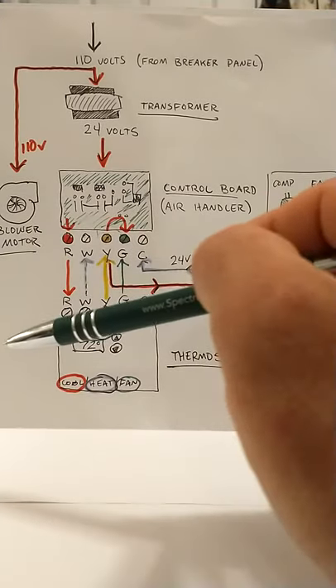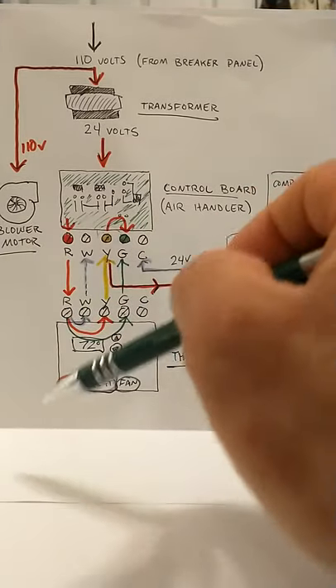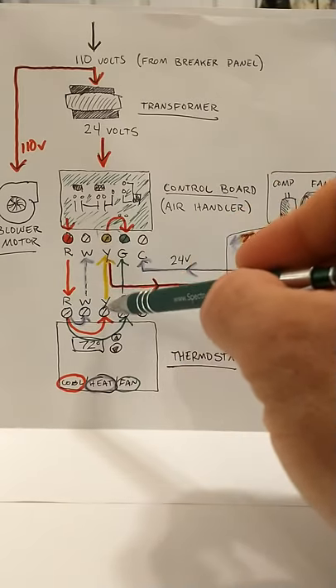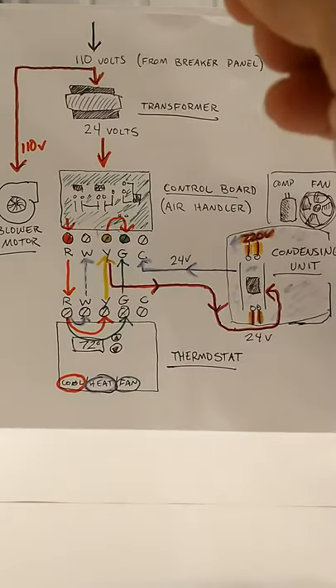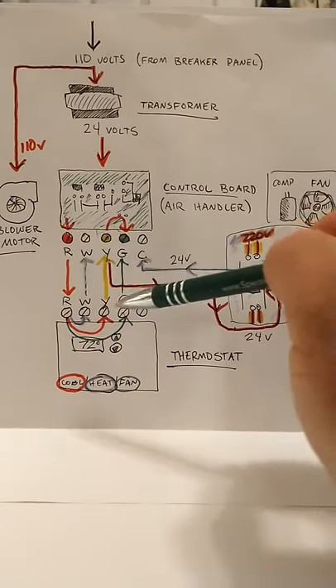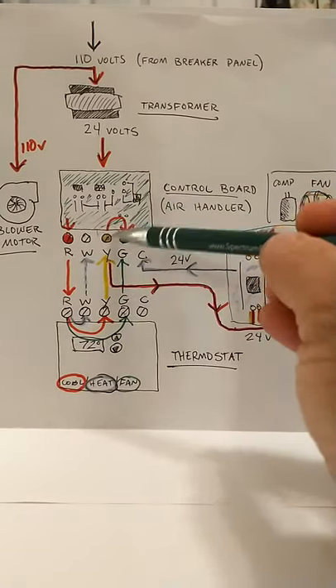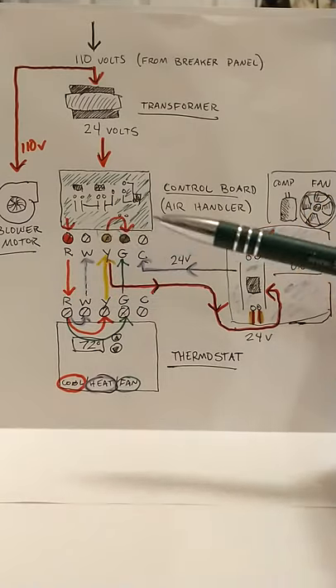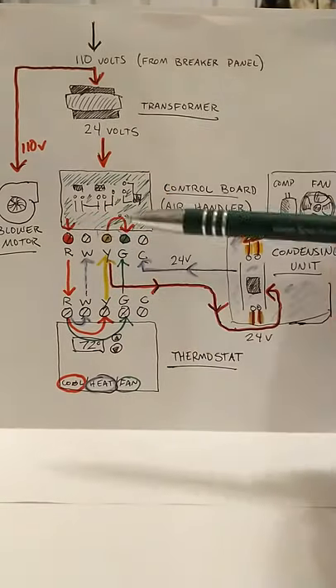So that when you're in cooling mode, if that float switch is lifted up, it will break that circuit and it will never allow the 24 volts to get from the thermostat to your air handler. And that'll prevent your blower motor, your condensing unit from kicking and starting up.